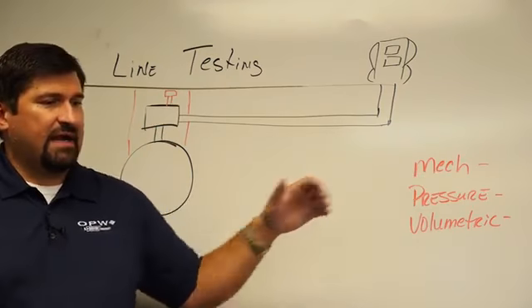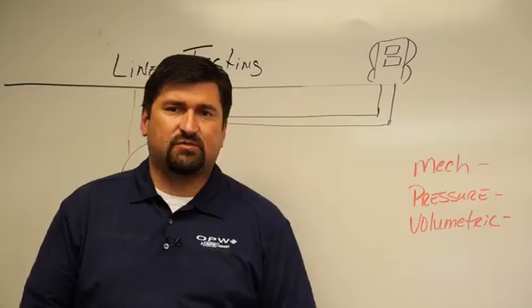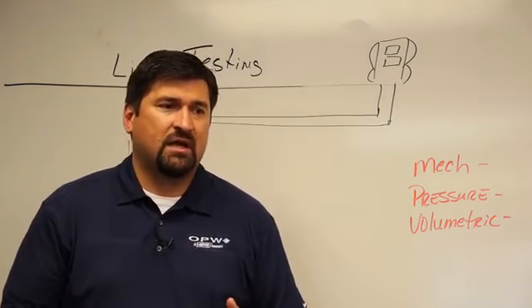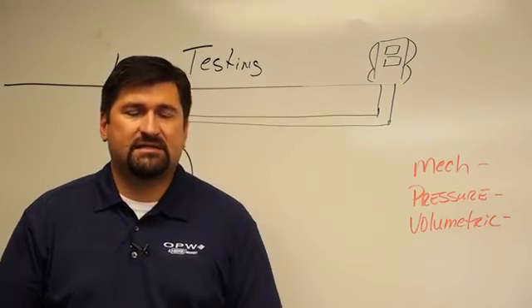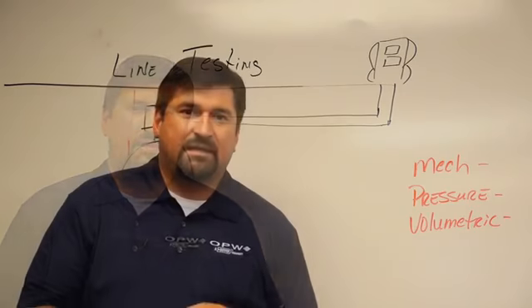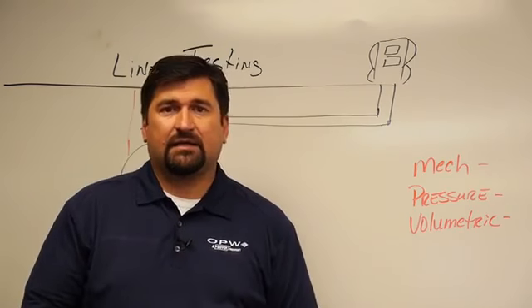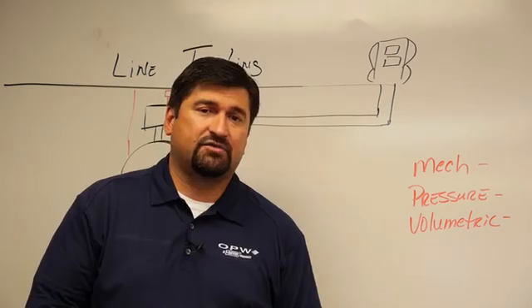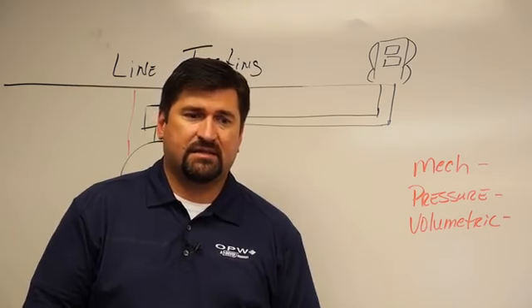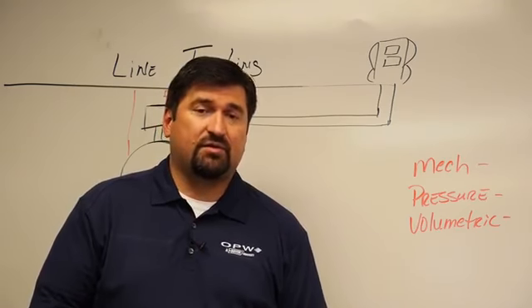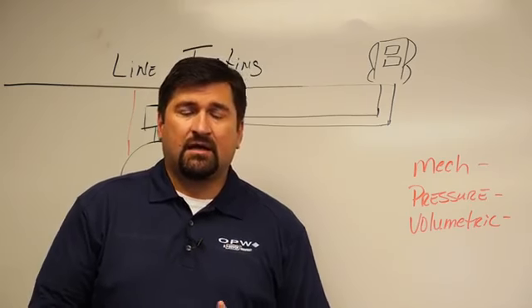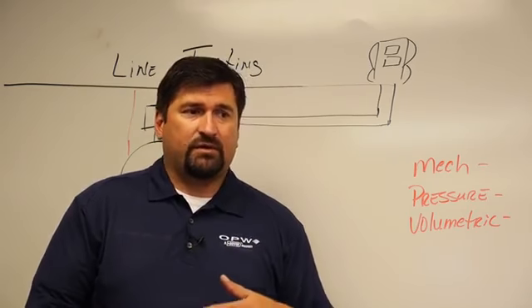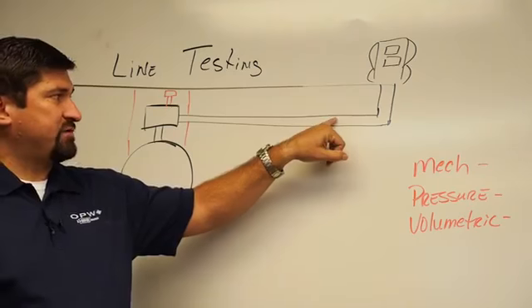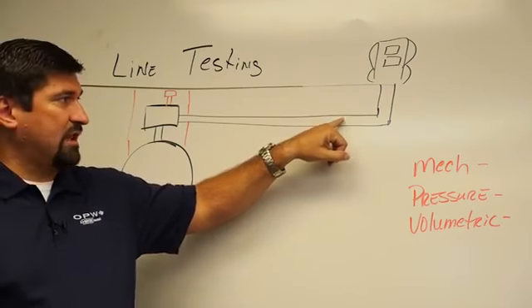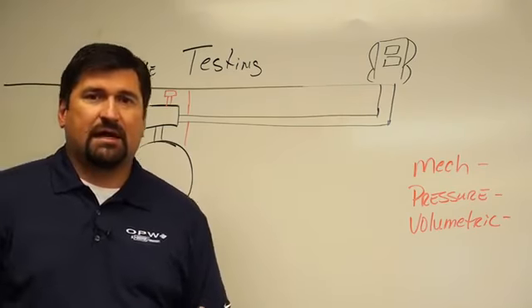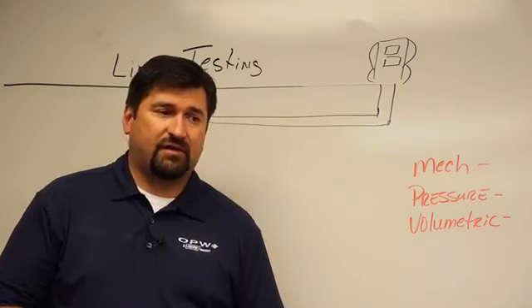It's a mechanical device. Well, when you start looking at mechanical devices, we talked about the regulatory requirements. A mechanical will have to be tested once a year. They will test the functionality of the mechanical line leak detector, and they'll test the functionality for it to trip on a 3 gallon per hour line test. But what they'll also do is a third-party certification on the line to a 0.1 leak rate. When they're doing that, they're just basically doing an overpressurization or a volumetric test on this line to make sure that the line is tight, and they'll get recertified for the year.